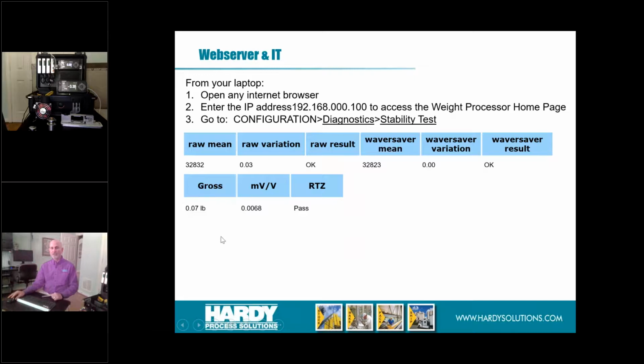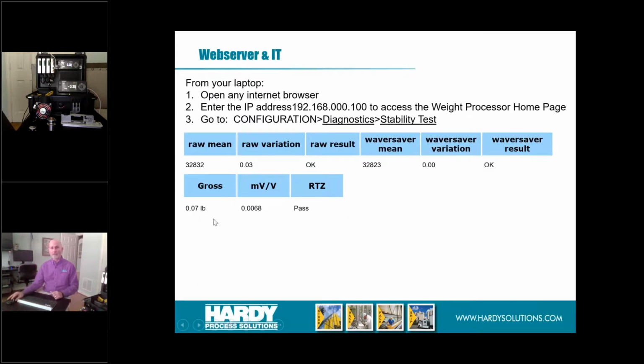This is where you can determine if a load cell has failed or not. If you had multiple load cells, you would have 4 different readings here. 3 of the 4 would be virtually the same, 1 would be different, and it's very easy to determine that the one that's different is causing you the issue.